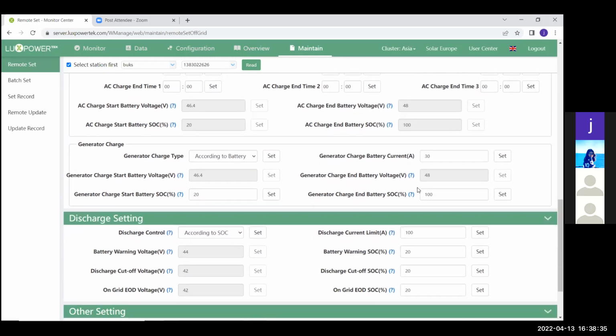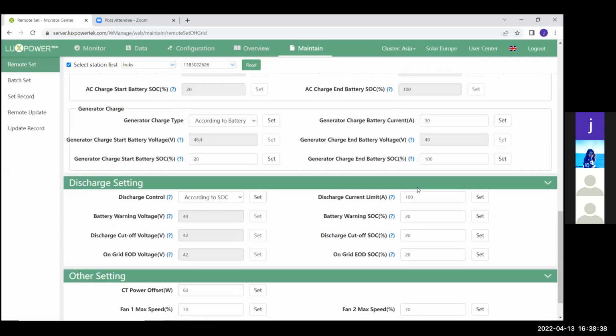Now, generator. This is a fairly easy topic to cover, but it's also a topic that a lot of clients don't understand very well. Your generator has to be within the acceptable range for my inverter to accept it. If you have a generator that fluctuates a lot with the volts and the hertz, there's a very good chance my inverter will see it, but it won't use the power because it's not happy with the stability of your generator source. Now, for you to be able to use a generator charge, your inverter has to be on the newest firmware. I'll also show you when I'm done with the settings how to update these inverters to the newest firmware using your own account. You don't have to contact us, you can do it yourself, and it's quite easy.